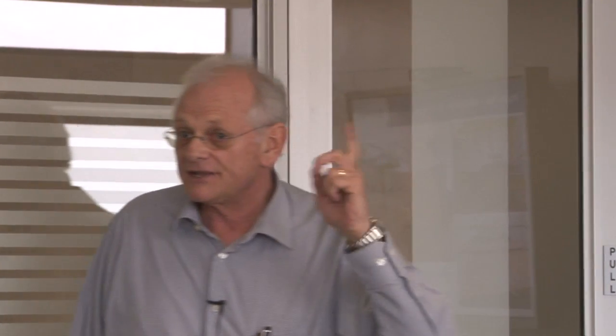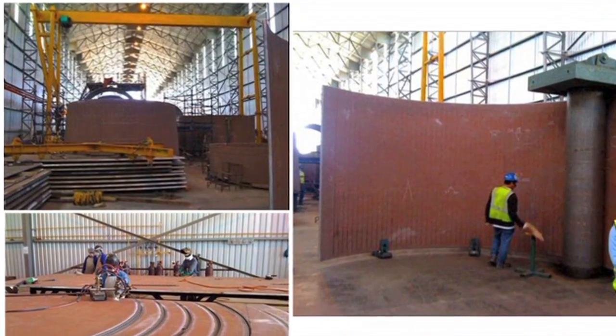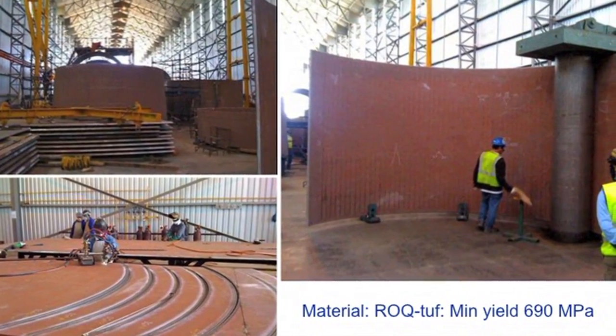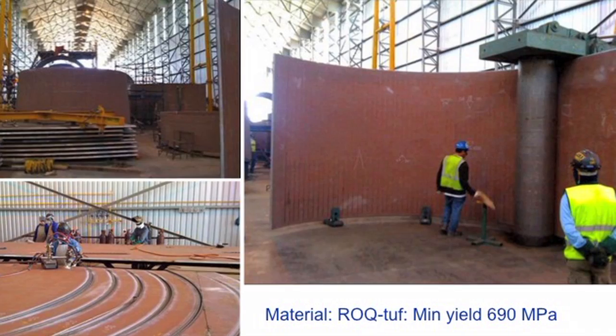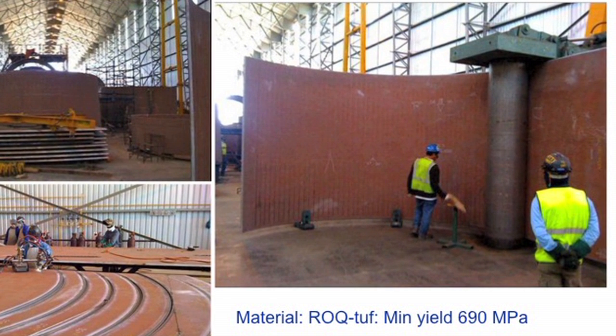Now, the pressure at transient condition is something, I think, 733 meters, which is quite a head. That needs to be contained, and we use ROQ-tuf steel for that at 690 megapascals. It was bent on site, as you can see, quite a big bending machine. And it was actually on the limit of this bending machine, because the steel that was delivered was actually closer to 800 MPa. So to yield the steel was quite an effort.